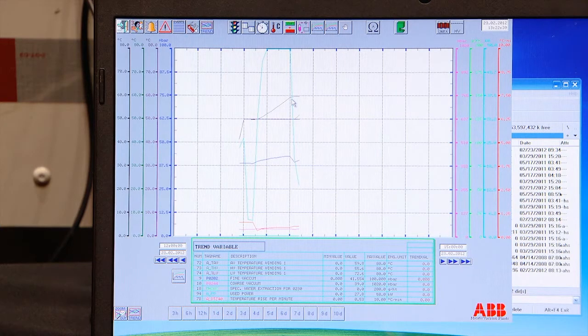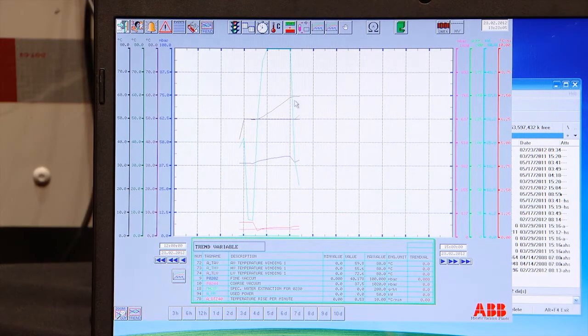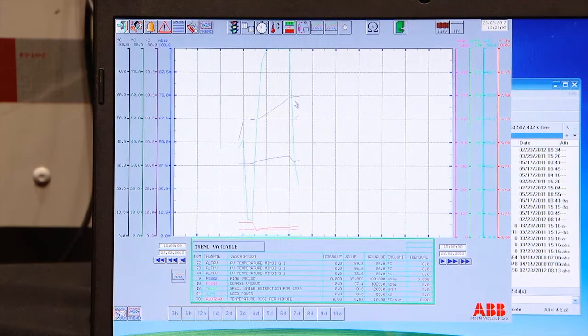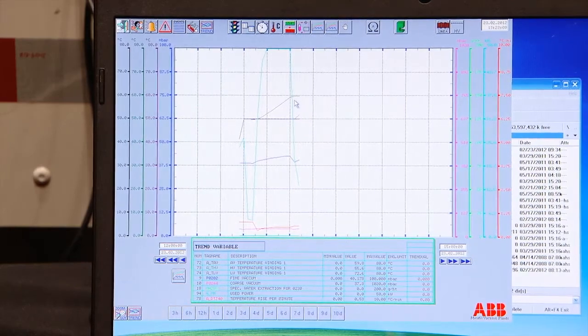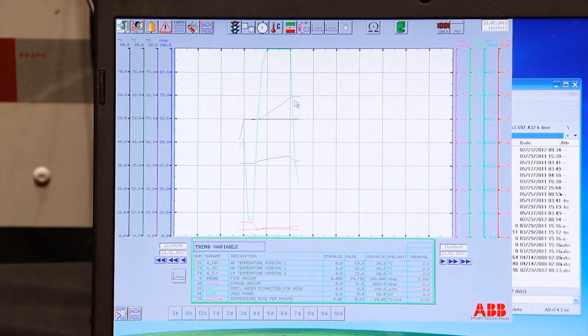I know it took half a year before the customer even accepted the factory acceptance test. And then when they came to site, they were able to dry 3 defined transformers, nothing else. What we have been working hard on is to get the resistance reading so accurate that we do not need a temperature sensor for following the temperature in the winding. Oh yeah.